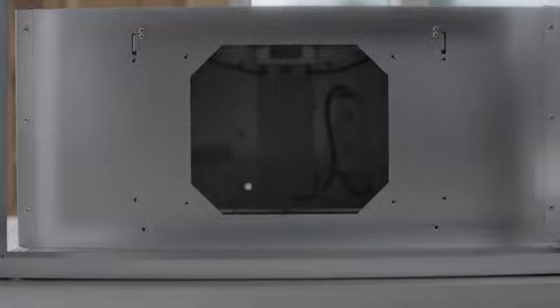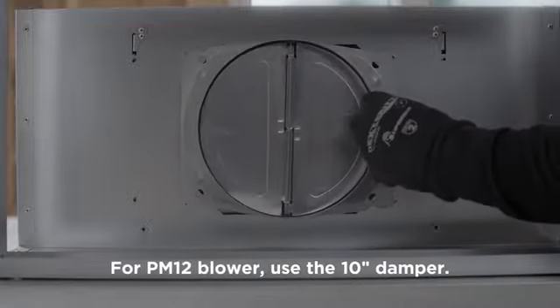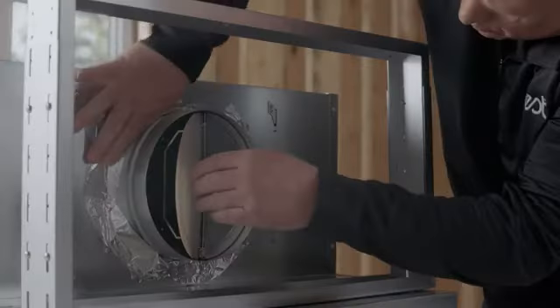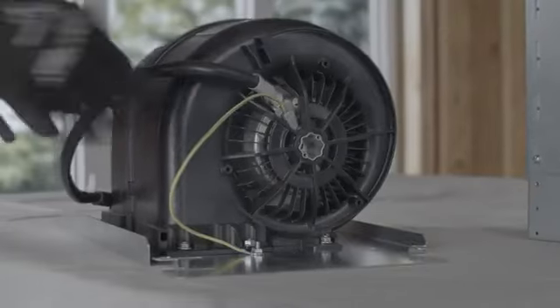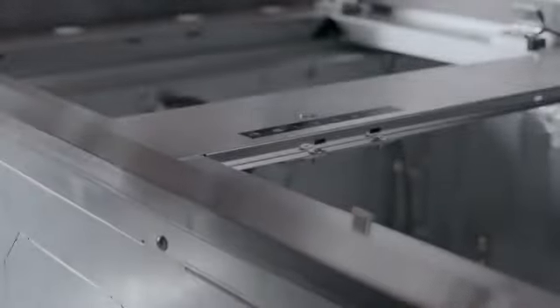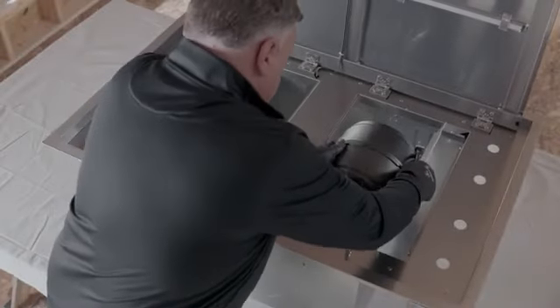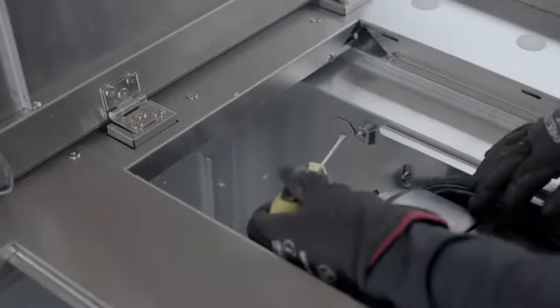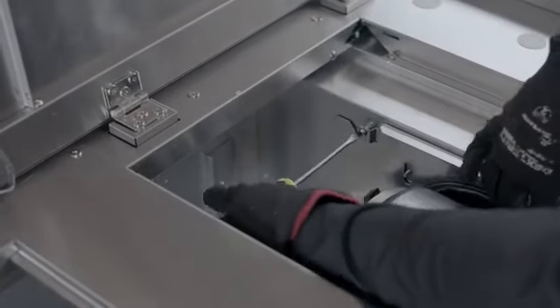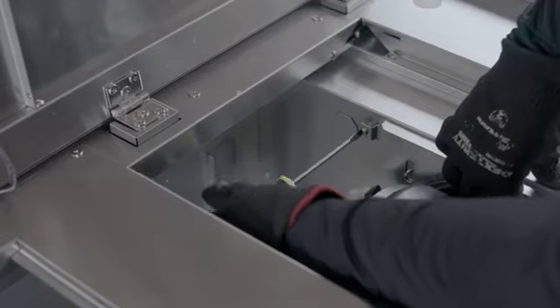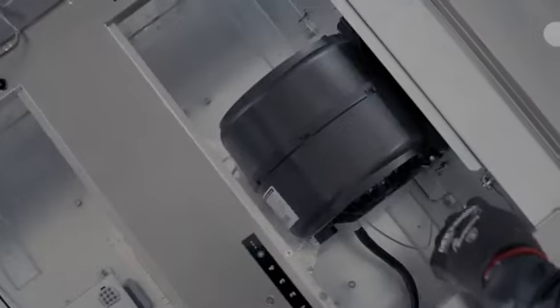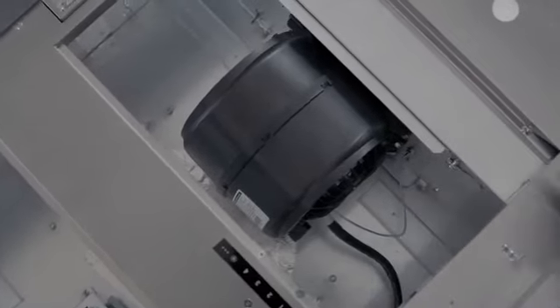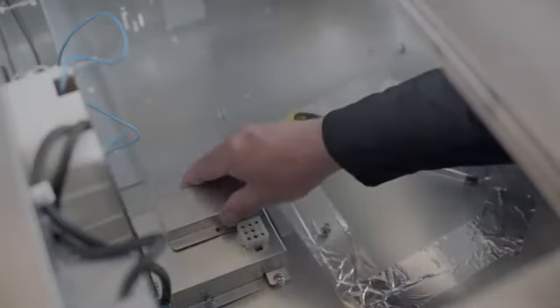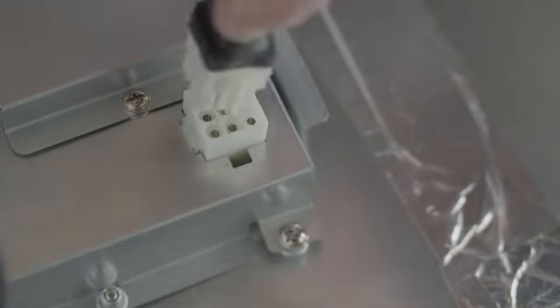When using the PM6 blower, you will need the 8-inch damper that is included with the hood. Since we are using the side exhaust discharge position, we can now install the blower and damper prior to installing the hood, although waiting to install the blower after the hood is installed reduces weight. Now, if installing the blower before mounting the hood, attach the blower plate to the hood in the desired position with the screws provided. Attach the ground wire from the blower to the ground stud. To connect the blower to the hood power source, swivel the connectors plate to unhide the connectors. Then simply plug the blower power cord into a connector.